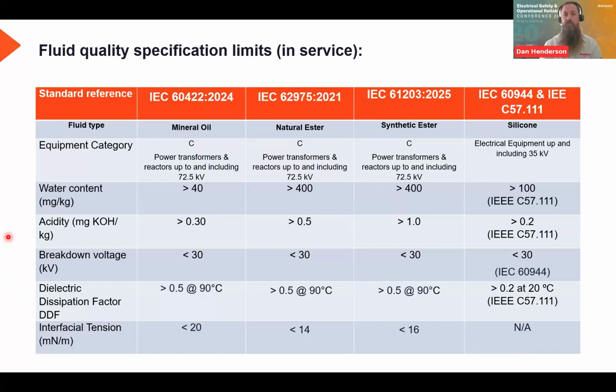what was going on inside there from paper debris being in the oil, any breakdown or increase in acidity. Obviously, if we went into a remediation, like recirculating the oil, there's potential there where we could rapidly increase that process by forcing the process, possibly by pumping across or drawing away across the windings, drawing out more paper or causing an increased aging process. So again, it's good to understand how all the results tie in, and then use that information to determine what your remediation actions are.